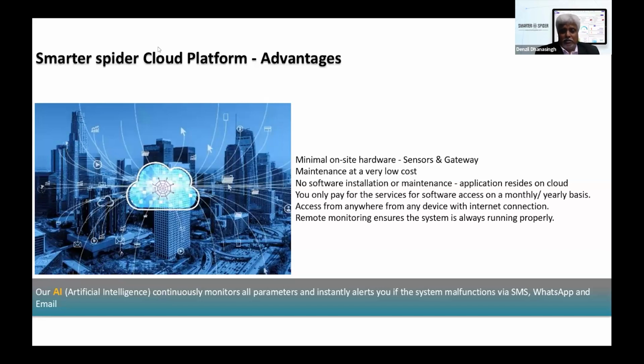What I'm talking about is a very minimal, lower cost to monitor these systems. That means additional sensors only at critical points, connected to a small gateway that takes the data into the cloud. The gateway collects data from the sensors. Even with big pipelines and a large pump house, you only need a few sensors at critical points connected to a gateway on site, which sends data to the cloud - and the cloud platform uses artificial intelligence to take action on it.